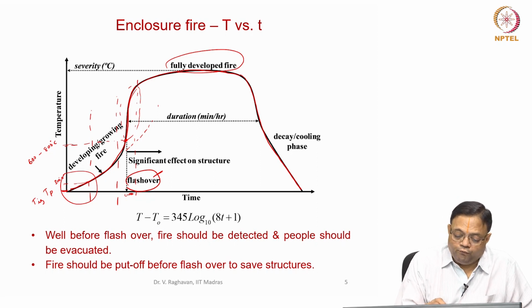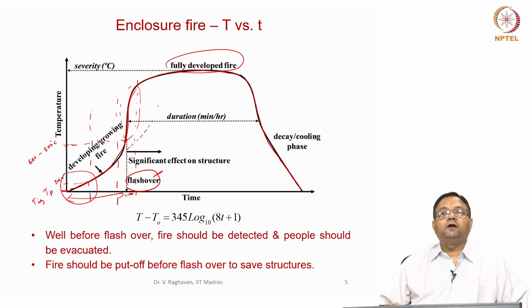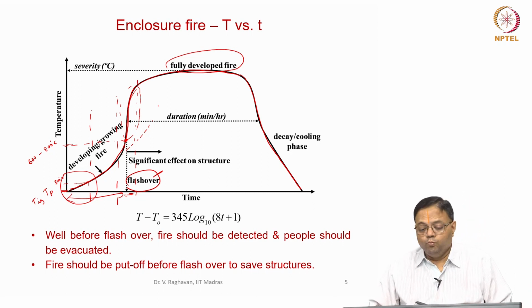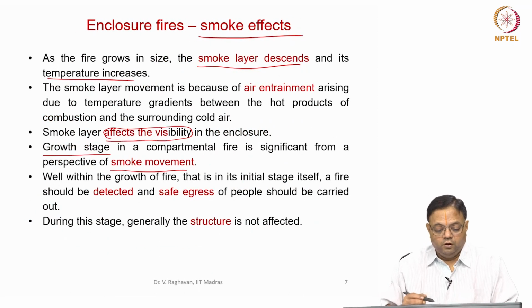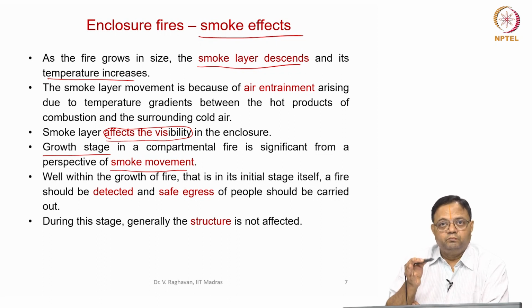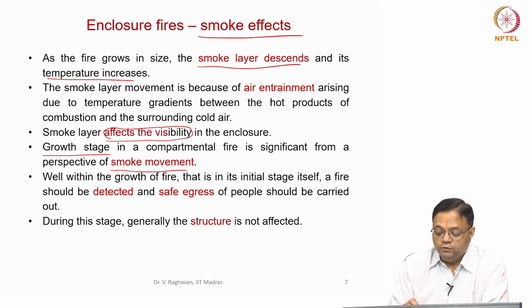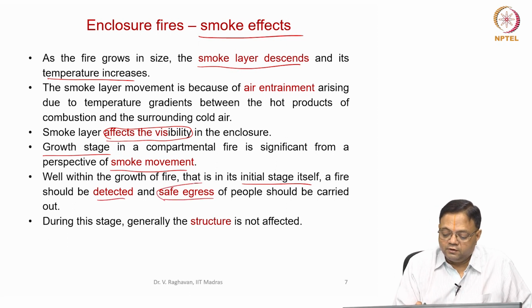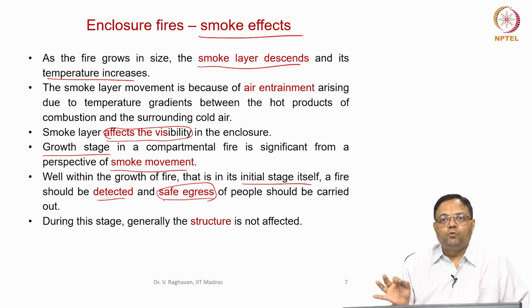Okay, now how fast you reach this, what is the time period for reaching this condition, is dependent on the smoke layer movement. Well within the growth of the fire, that is before the critical condition or flashover condition is reached, that is the initial stage, we can say, the fire should be detected and safe egress, that is removal of people, should be carried out.